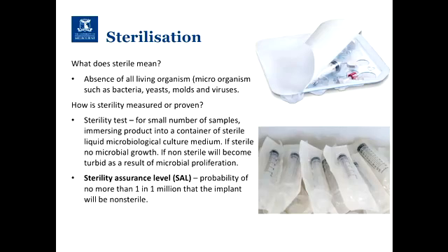Because we can't say that everything will come out sterile 100% of the time, there's a baseline that medical device companies sterilise their devices to: the probability of no more than 1 in 1 million of whatever is going through being sterilised is actually non-sterile.